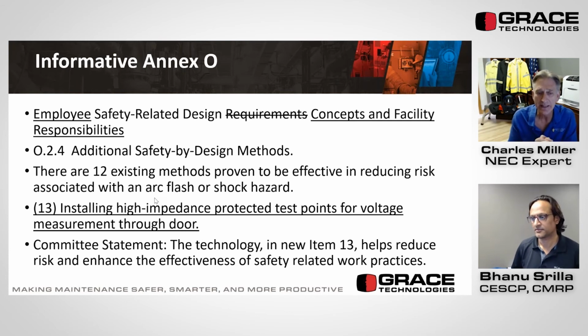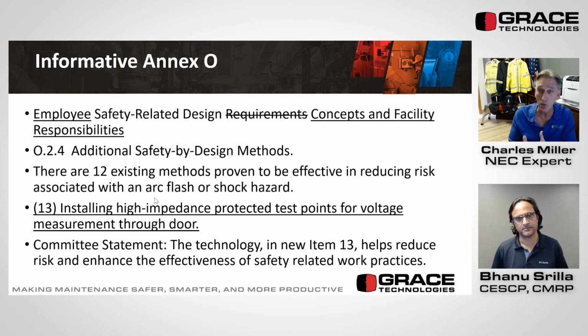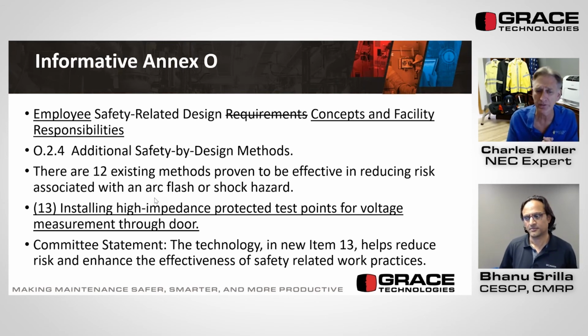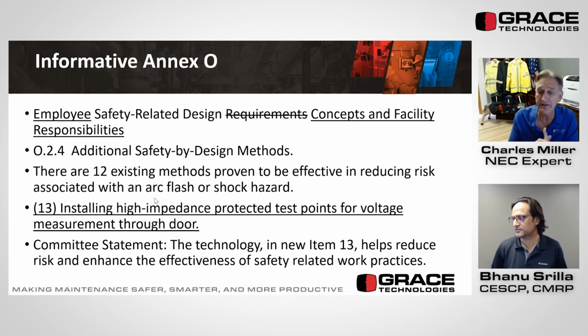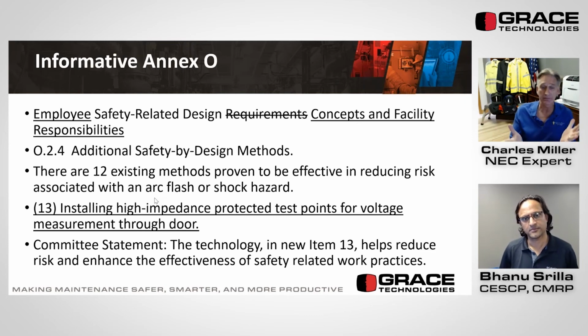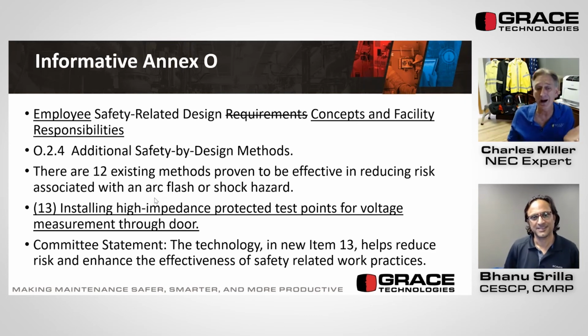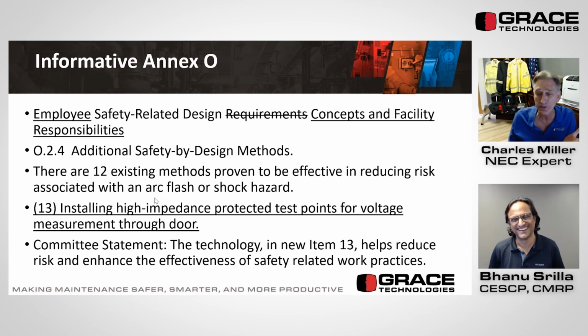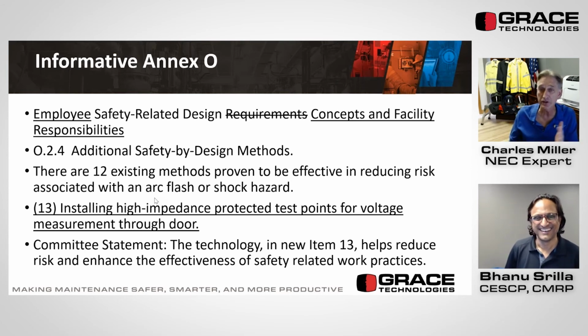Number 13: installing high impedance protected test points for voltage measurement through the door. Committee statement on this: the technology in new item 13 helps reduce risk and enhance the effectiveness of safety-related work practices. Now, what are they talking about? High impedance protected test points for voltage measuring through the door.